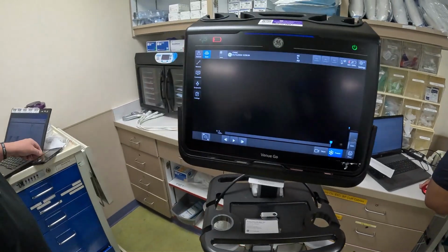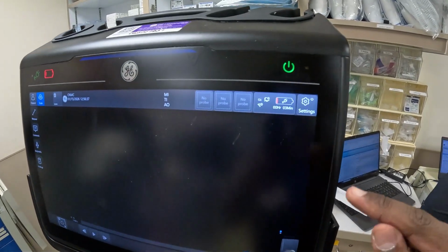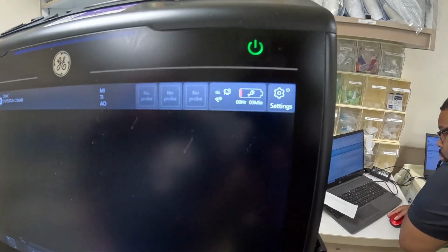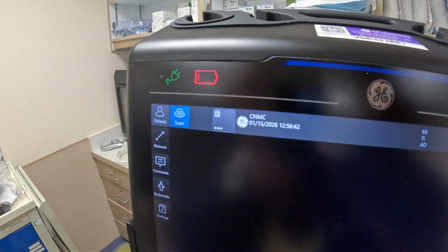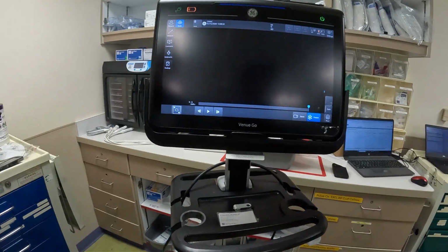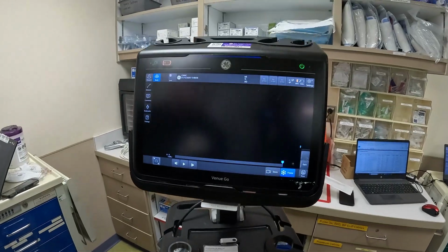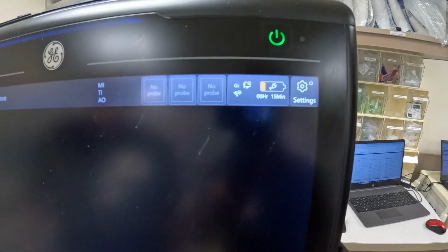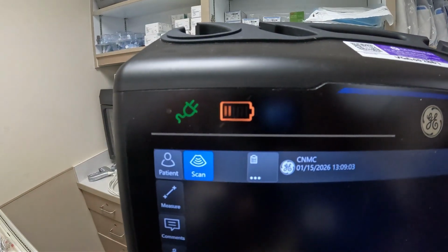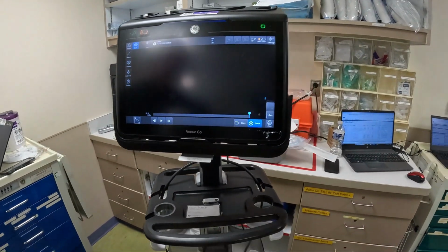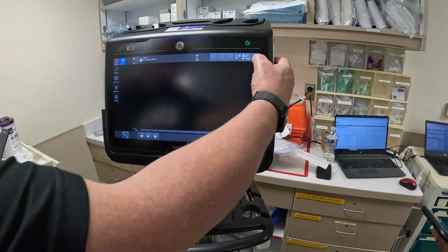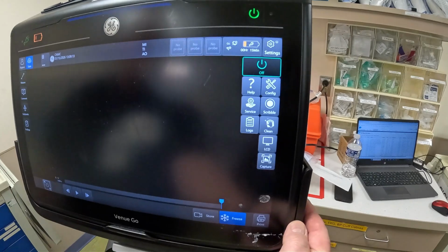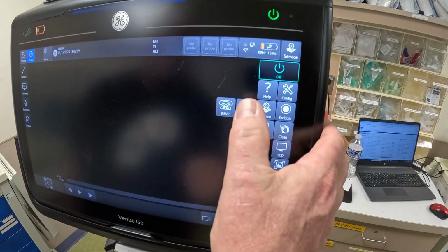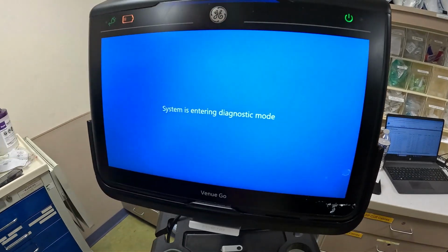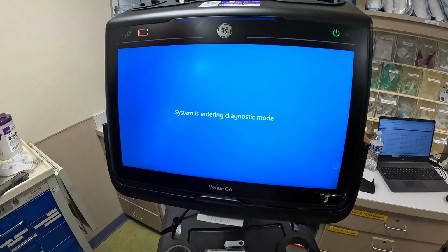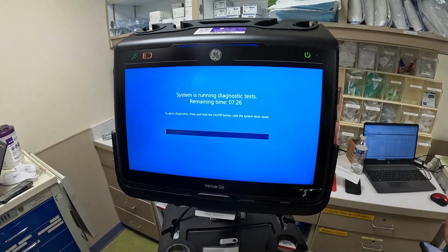Now, you must wait for it to charge until you see about 10 minutes on the battery symbol, or 2 bars on this battery symbol. Once the ultrasound has been charged up a good amount, And you said 10 minutes? Yeah, at least at 10-minute mark, or 2 bars. 2 bars. Okay. You can now start the pre-diagnostic test. You go to settings, you go down to service there, and you click diagnostic. And now system is entering diagnostic mode, and it says it will take about 7 minutes and 26 seconds.